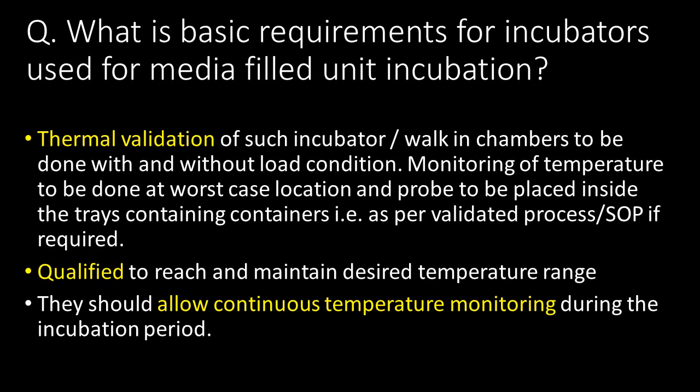Next question: what are the basic requirements for incubators used for media fill unit incubation? Thermal validation of such incubators or walk-in chambers must be done with and without load conditions. Temperature monitoring should be done at worst-case locations, with probes placed inside trays containing containers. These incubators shall be qualified to reach and maintain the desired temperature range, and should allow continuous temperature monitoring during the incubation period.